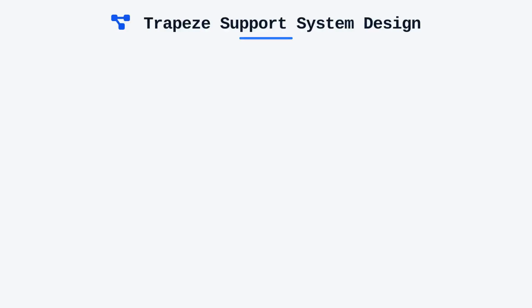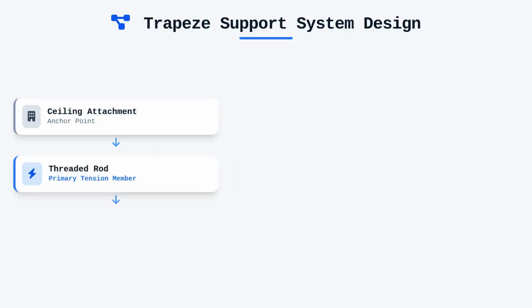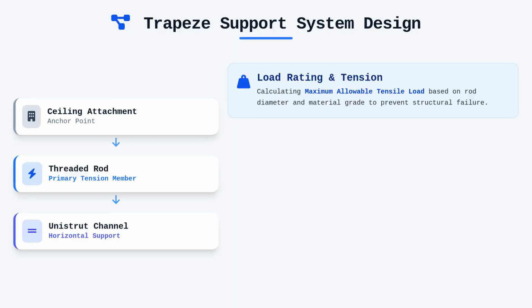Designing a trapeze support system using unistrut and threaded rods requires a methodical approach to geometry and load rating. The threaded rod, which acts as the primary tension member, represents the bottleneck of the mechanical connection between the ceiling and the cable tray. We calculate the maximum allowable tensile load of the rod based on its diameter and material grade, typically using standard steel rods that provide a high margin for structural safety.